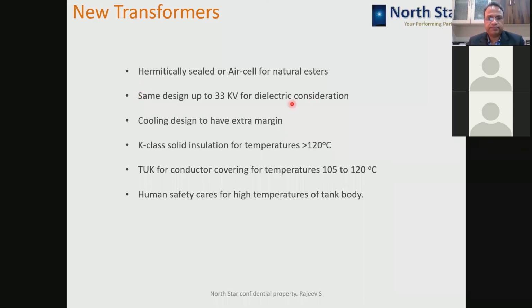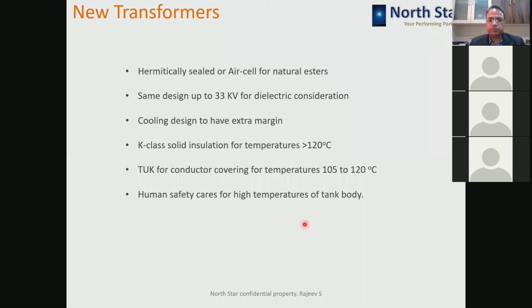Cooling design should have an extra margin, okay, because of the viscosity of these materials. If you are using K class solid insulation, like maybe Nomex, or fiberglass based insulation, then you can take the operating temperature to even more than 120 degrees centigrade. If you are using thermally upgraded kraft for the conductor with these liquids, then you can cross the 105-degree limit and you can very well operate the transformer at 120 degrees centigrade. Because they are working at high temperature, a touch can cause a burn. If somebody touches the transformer, then he or she can get a burn. So human safety at high temperature has to be adequately considered.